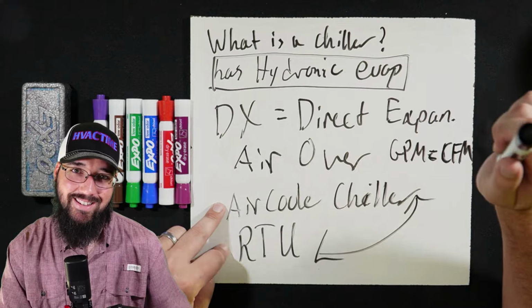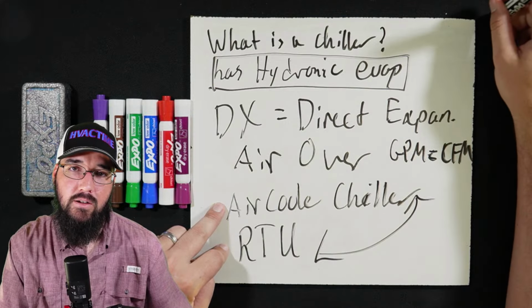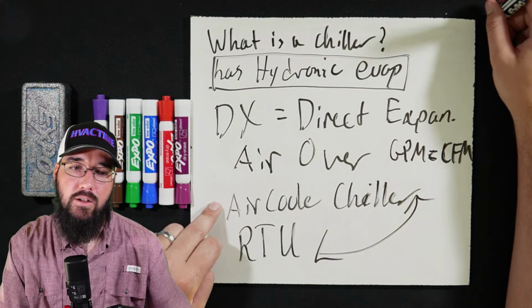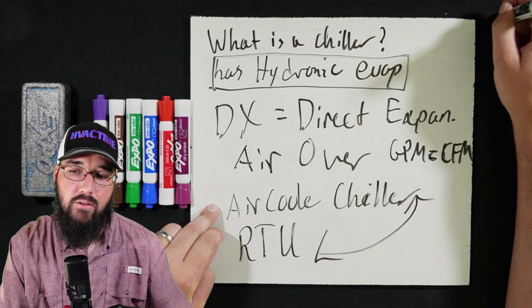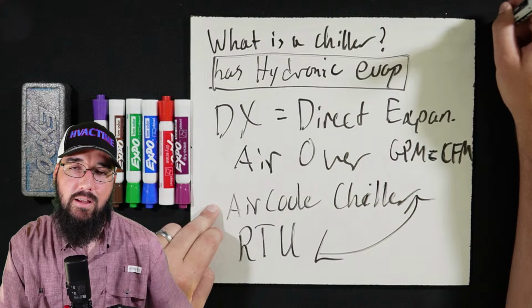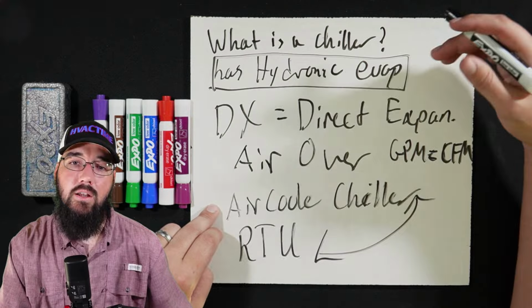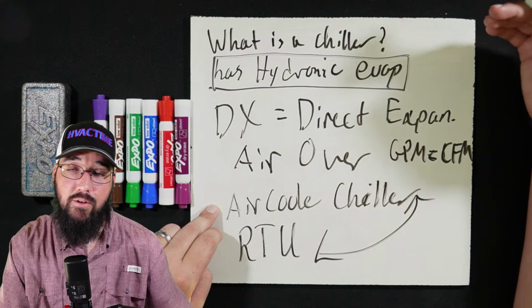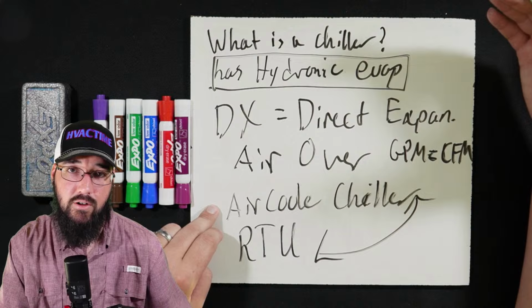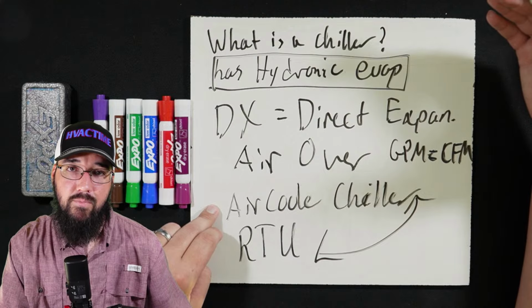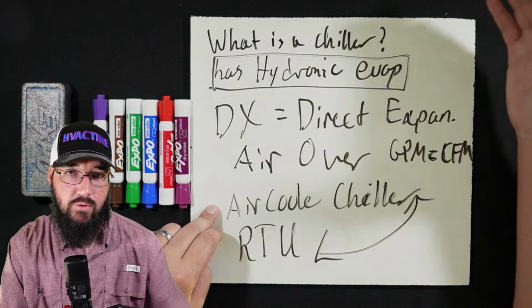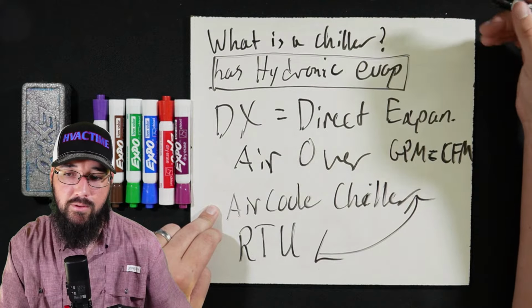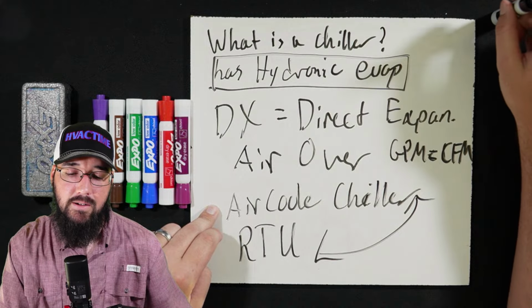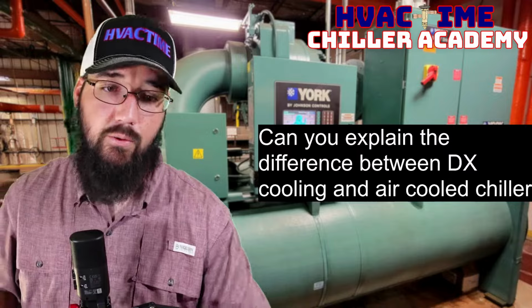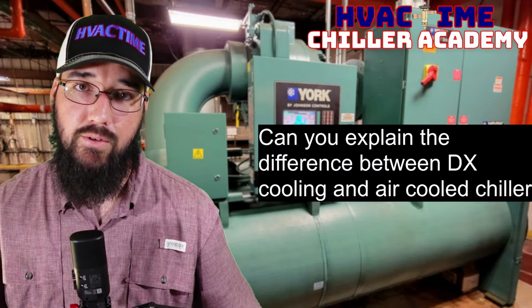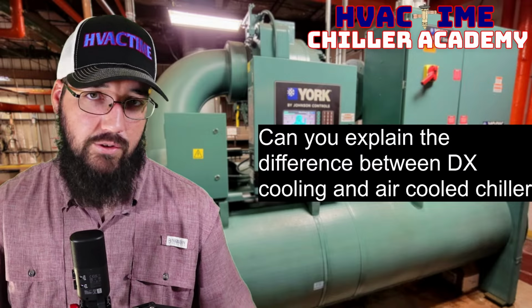Okay, translate that exact same troubleshoot into GPM. You tripped low suction pressure. What's my pump doing? Is it running? Do I have pressure? What's my differential pressure across my evaporator? It's no different than taking differential static pressure across an evaporator. So much of those concepts are translatable right back and forth between them. Anyway, that is my answer to the question of explaining the difference between a DX and an air-cooled. It comes down to that on just a pure fundamental scale.